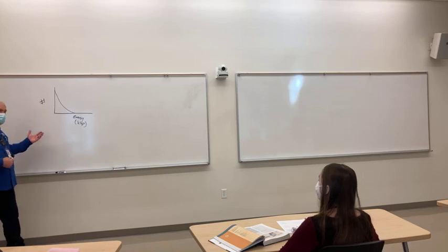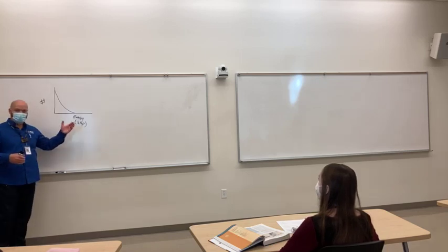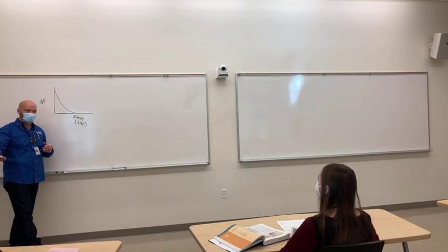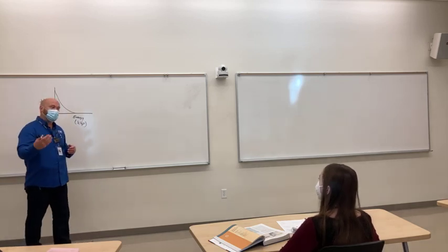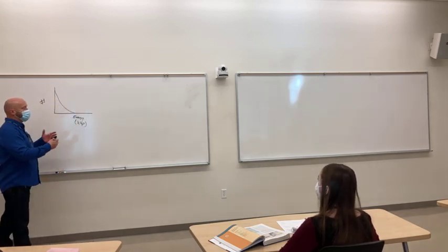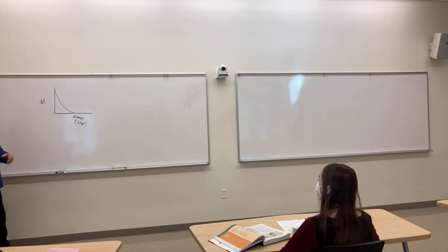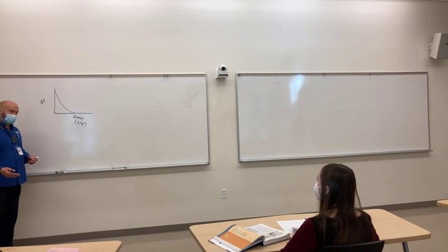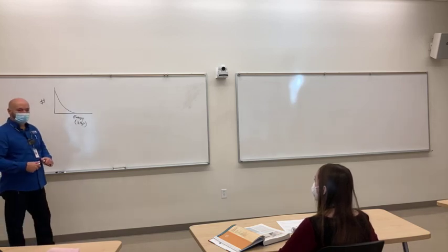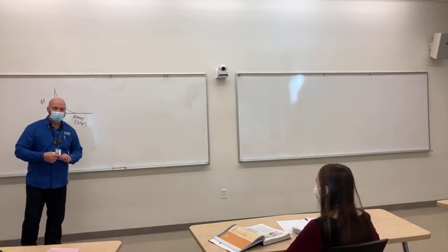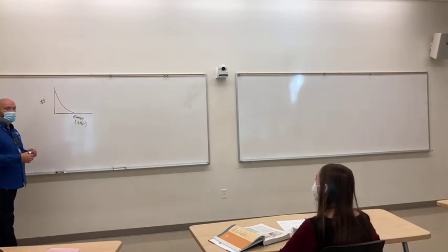But we don't expose the patient to the X-ray beam just as it leaves the target, right? We expose the patient to the X-ray beam as it leaves the collimator housing, or you should be anyway. So what does it have to pass through to get through the collimator housing? What's the first thing it's going to hit? The glass or the metal envelope, right?